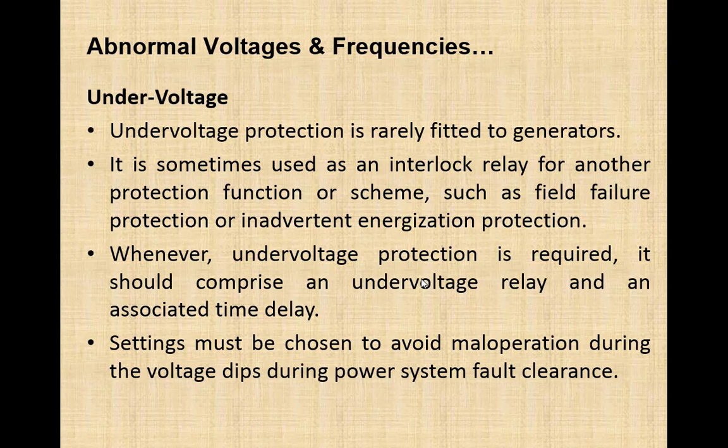So the motor starting mechanism will have this protection. A simple way to provide under voltage protection is a contactor whose coil is energized with voltage, and the contactor is used to start the motor. As soon as voltage will be less than the rated value of contactor coil voltage, the contacts will drop out and motor will get isolated from the system. And if voltage will be less, then we will not be able to close that contactor to start the motor. So that is under voltage protection of motor in case of small motors. So under voltage protection is mandatory for motors.